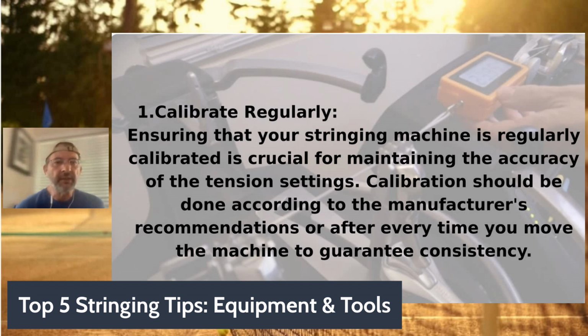The idea here is, anytime you move the machine from one location to another, or you move it for a little while and then move it back—any of those situations—I'd recommend rechecking the calibration to make sure nothing got jarred or moved around inside the machine, so it's as accurate as before.